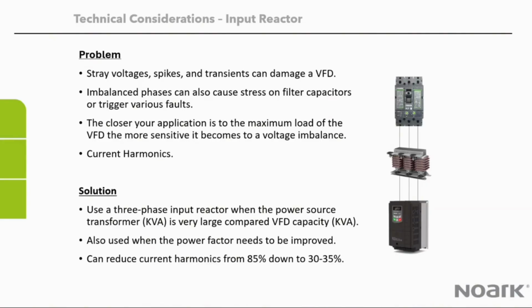When should I consider an input reactor? Well, if you're experiencing stray voltages, spikes, imbalances, or you're running the drive close to its maximum, if there's any harmonics, using an input reactor would allow you to overcome that, would improve your power factor and reduce harmonics.